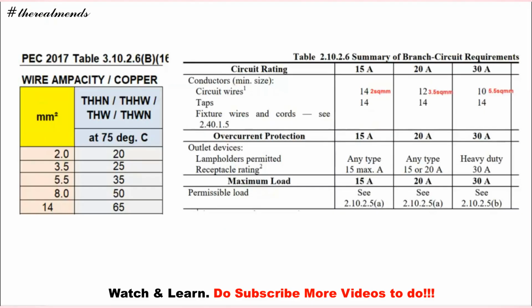So, from the PEC table 3.10.2.6 B16, meron tayong wire ampacity, so mm squared, THHN, THWN at 75 degrees Celsius. So, pag 2 square mm, 20 amperes. Pag 3.5, 25 amperes. Pag 5.5 square mm, we have 35 amperes. 8.0, we have 50 amperes. Pag 14 square mm, 65 amperes yung kanyang ampacity at 75 degrees Celsius.